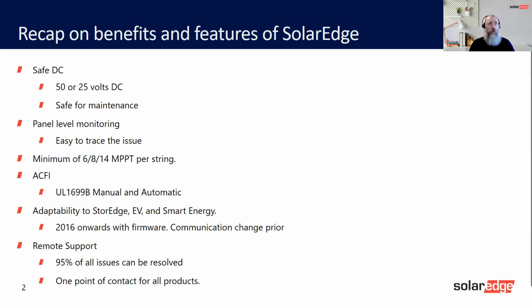Remote support, because all of our systems, we prefer them to be online. We would say that 95% of all issues we can diagnose and resolve remotely. So we can monitor your system as you can, but we can dial into the optimizers. We can talk to the optimizers. We can talk to the inverters, and we can see different things. We can adjust the settings on the optimizers and the inverters as well. So we're confident we can resolve 95% of all issues without you having to go to site.